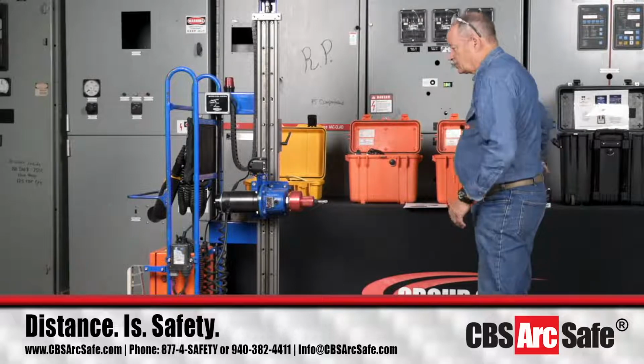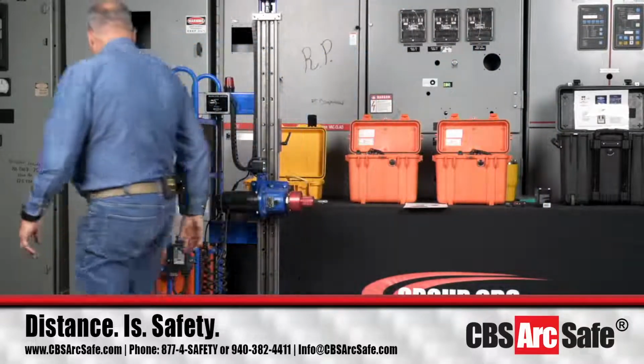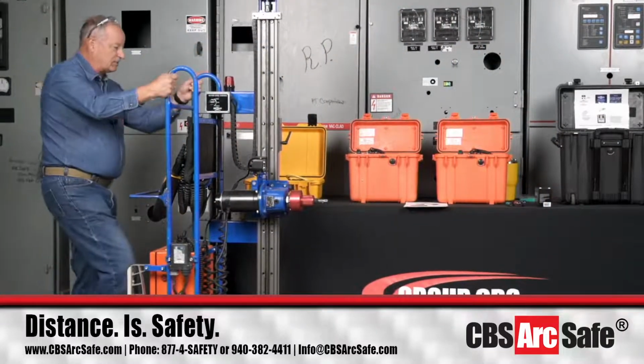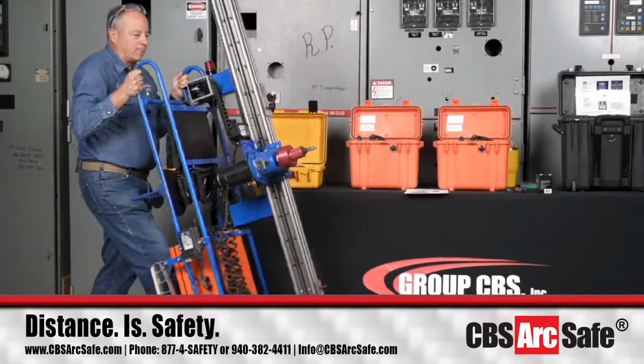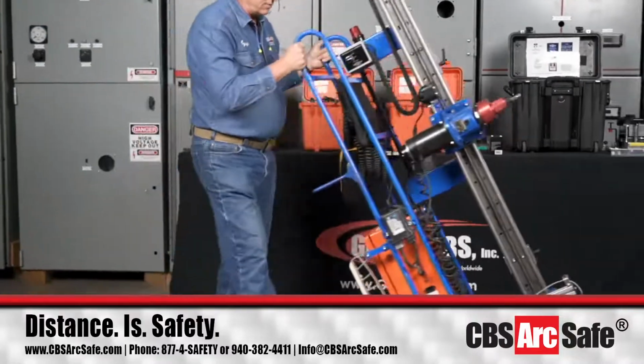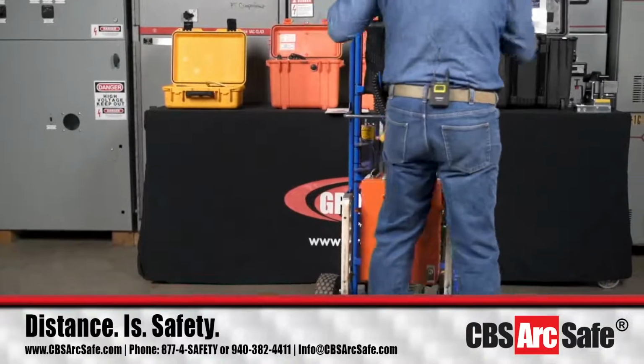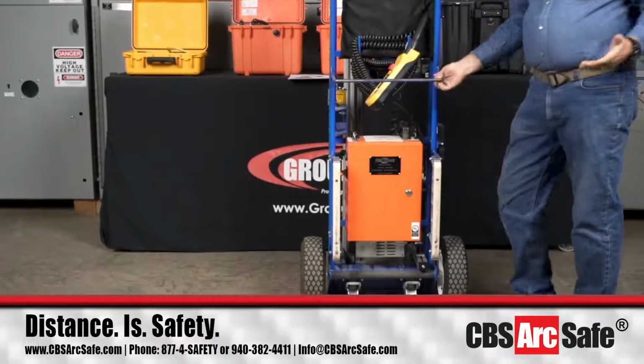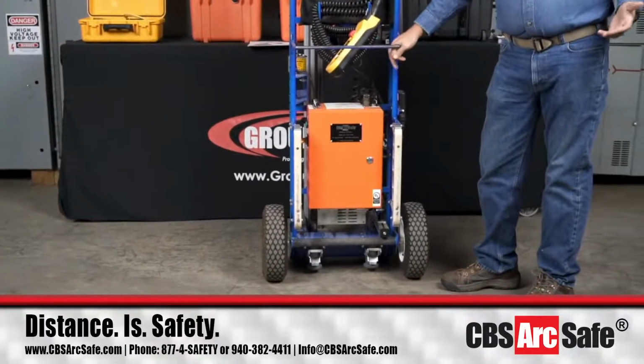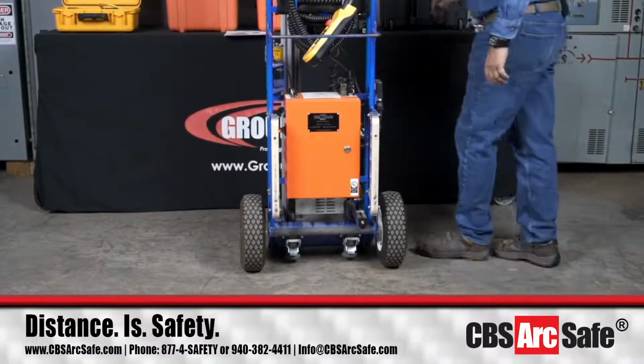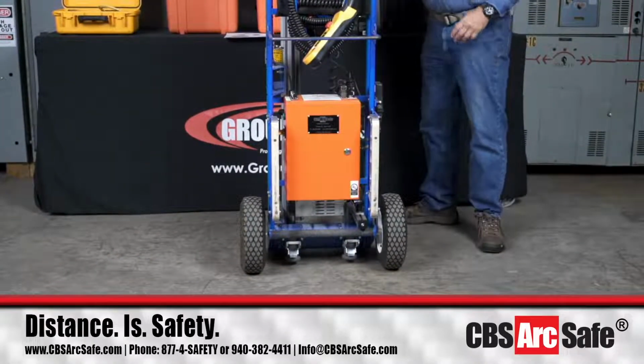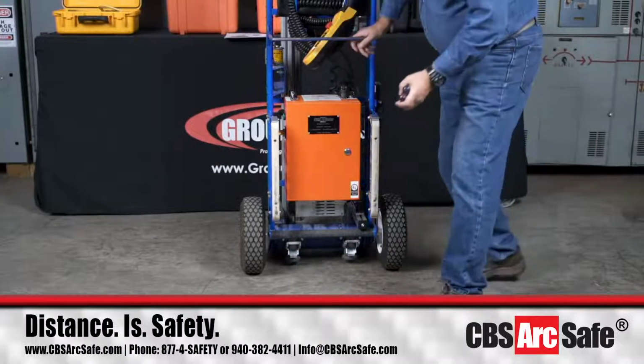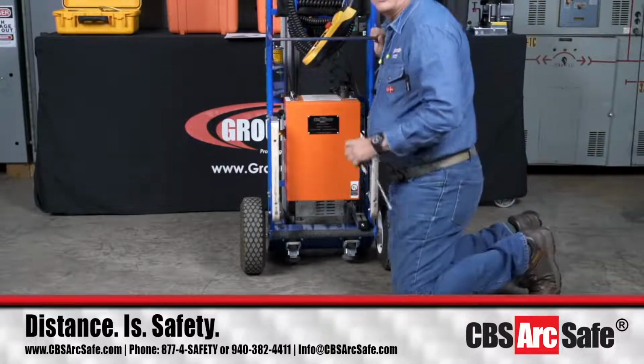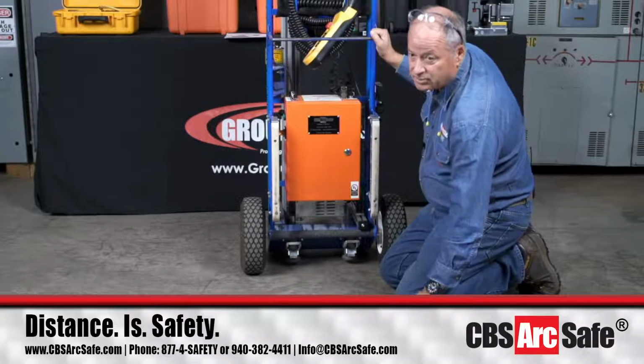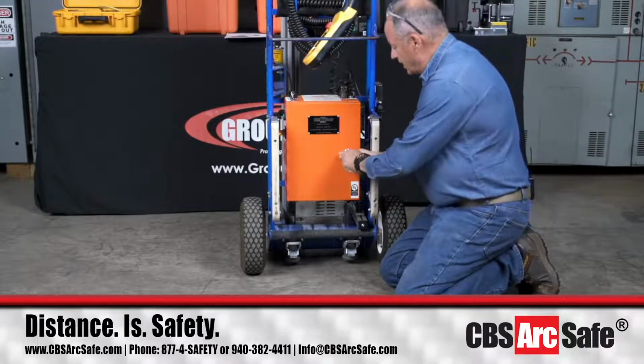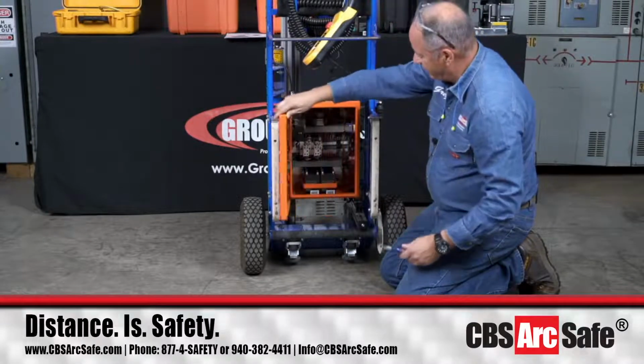So with an RS1, to change the batteries and inspect them, you'd normally use your Fluke meter or whatever voltmeter you use. You would open this up, and we recommend checking it once a year. The battery manufacturer recommends replacing them every 2 to 3 years. We've seen customers have them last longer than that, and we've seen customers run these things down and kill them in a rapid fashion.